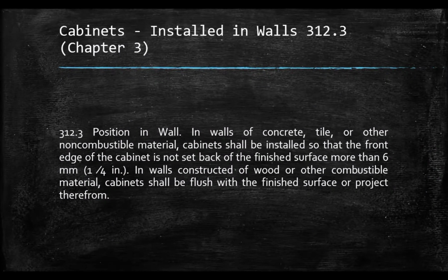Cabinets installed in walls, 312.3 from chapter 3. 312.3 Position in wall. In walls of concrete, tile, or other non-combustible material, cabinets shall be installed so that the front edge of the cabinet is not set back of the finished surface more than 6 mm or 1/4 inch. In walls constructed of wood or other combustible material, cabinets shall be flush with the finished surface or project therefrom.